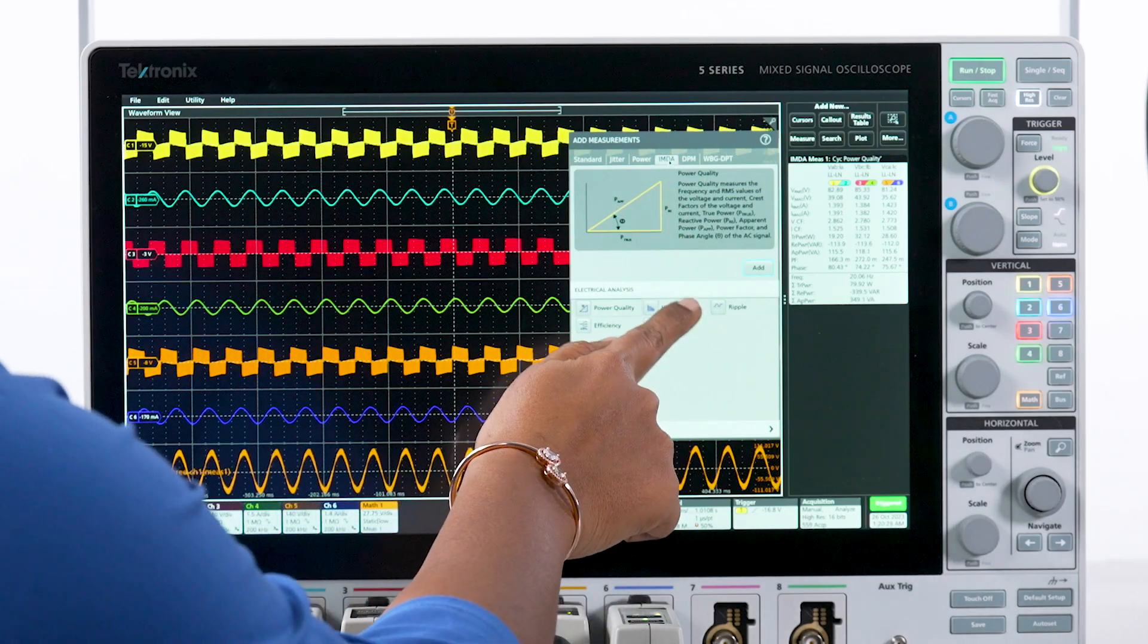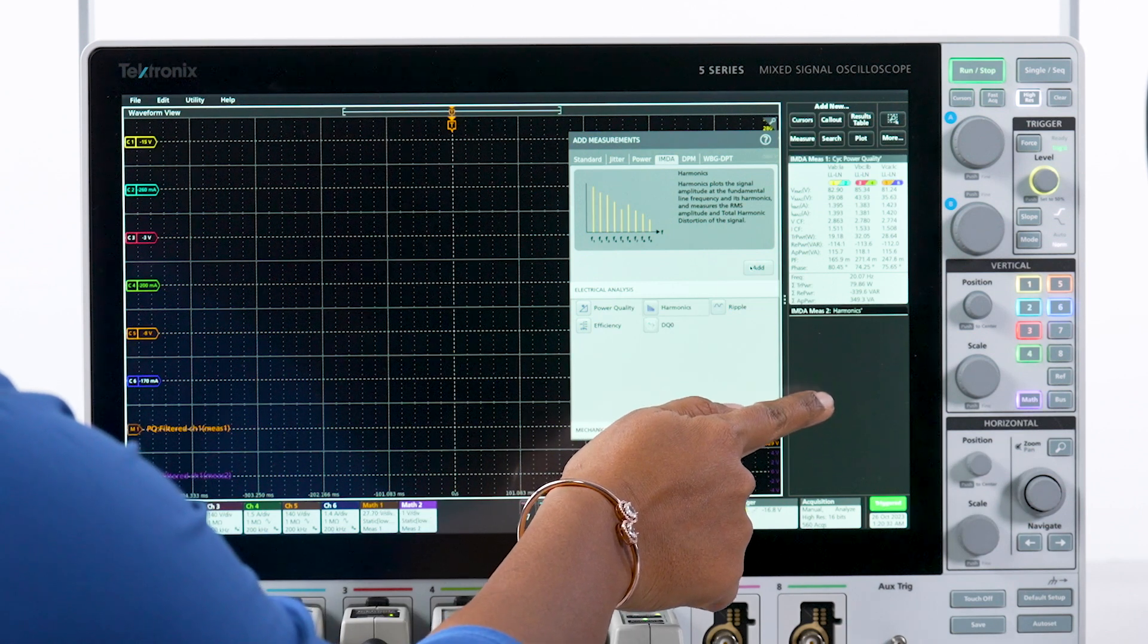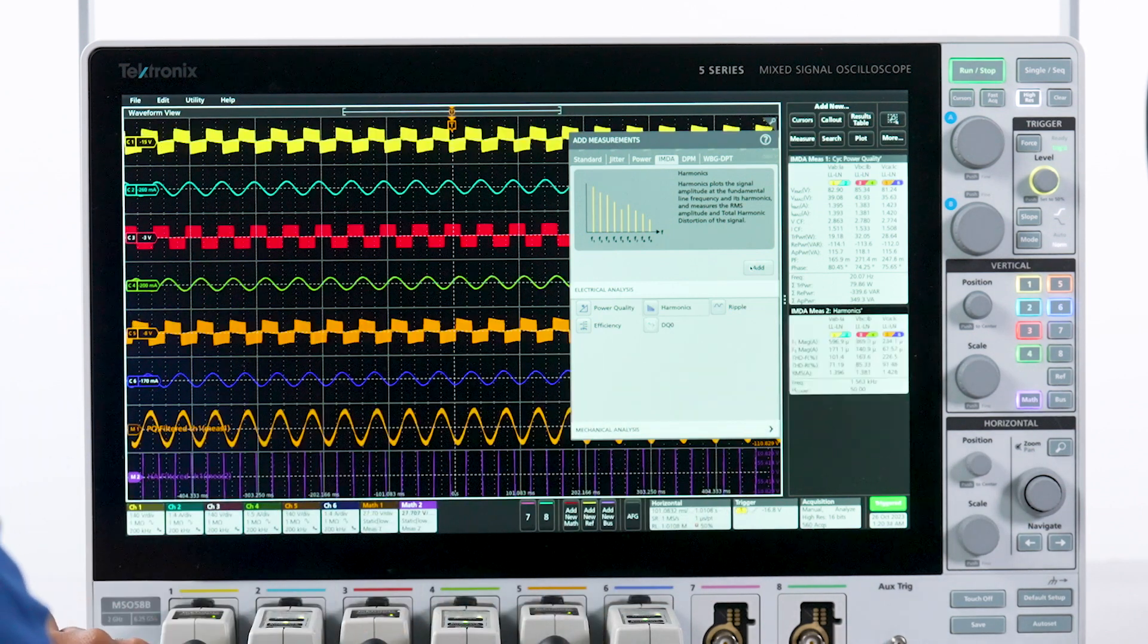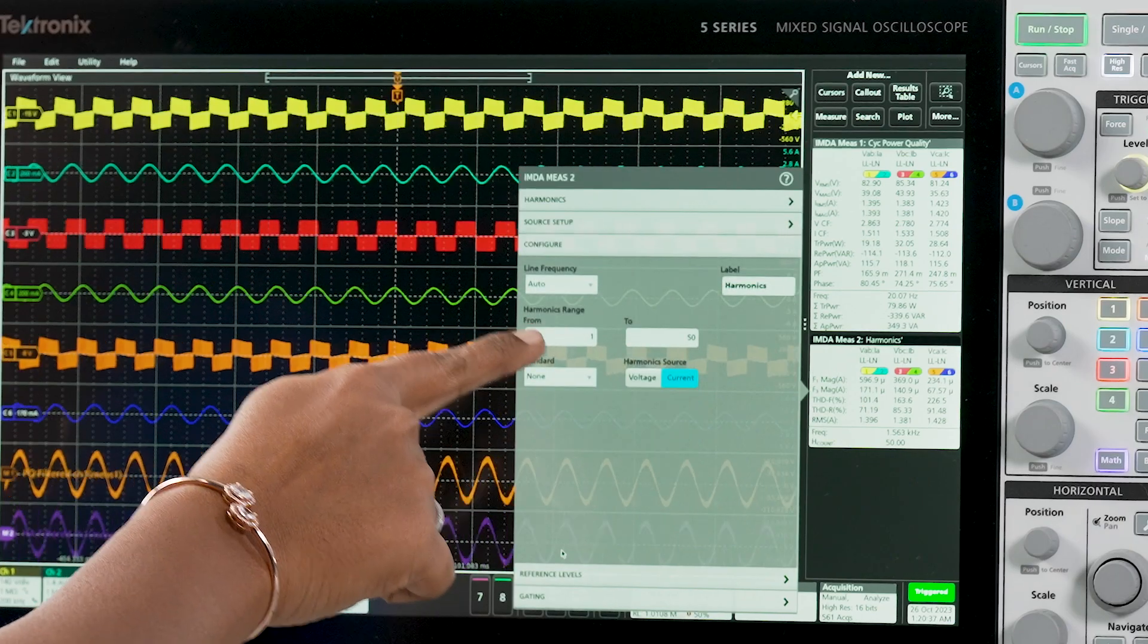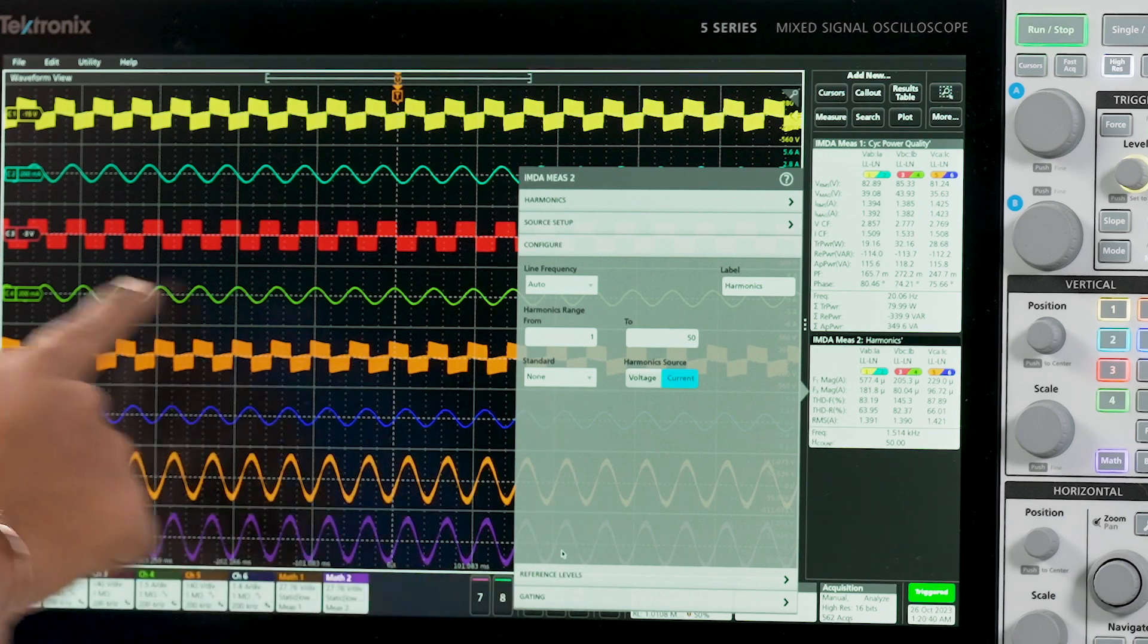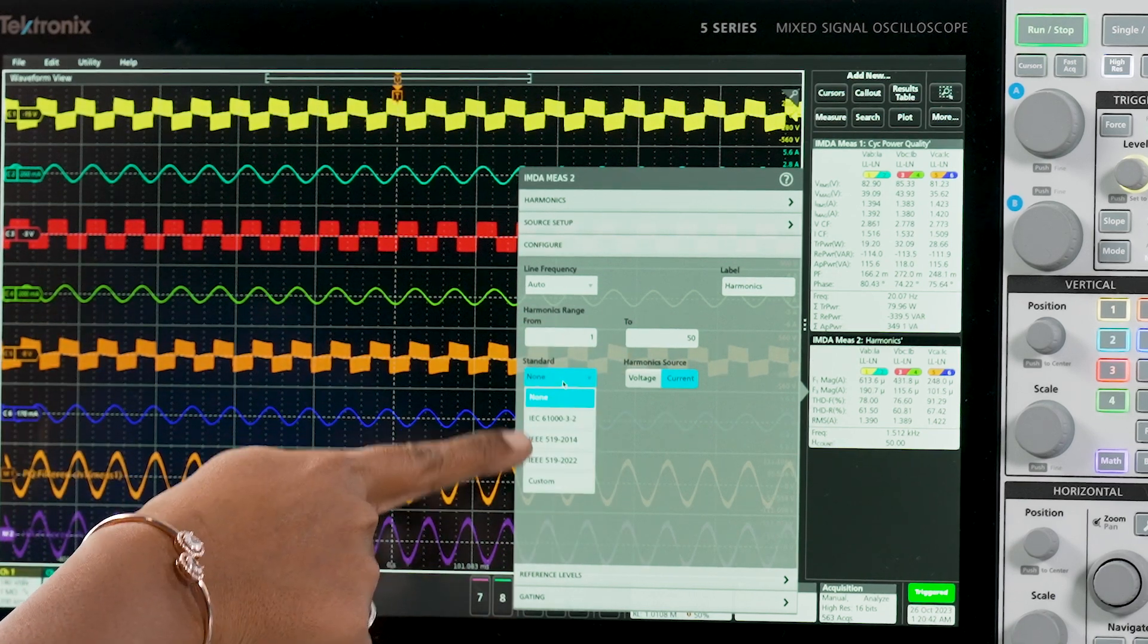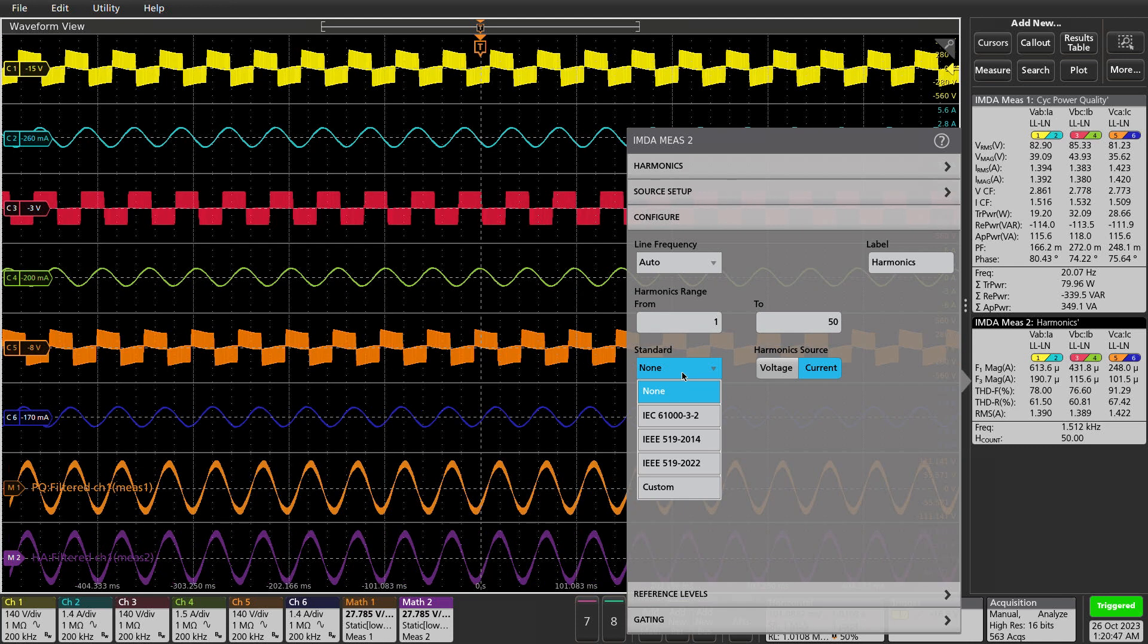Voltage and current harmonics can be displayed as bar charts for all three phases, along with total harmonic distortion and total demand distortion. I can measure three-phase harmonics per IEC 61000-3-2, IEEE 519, or custom limits.